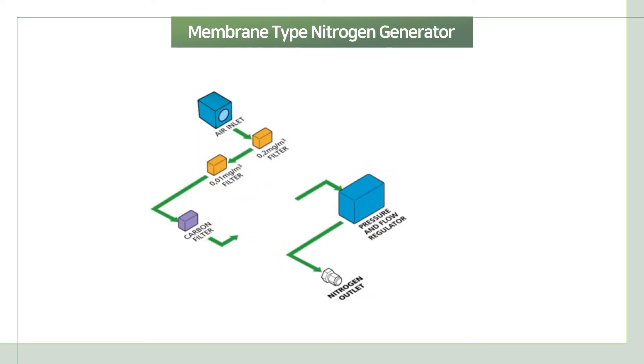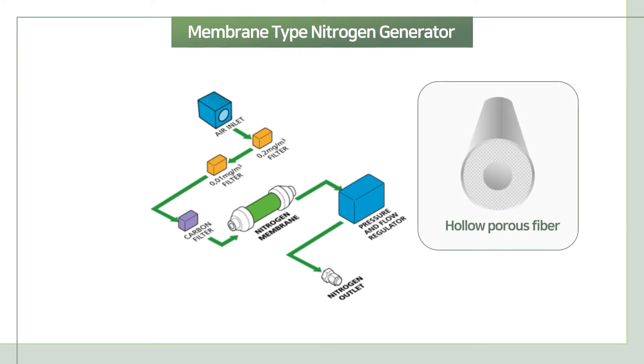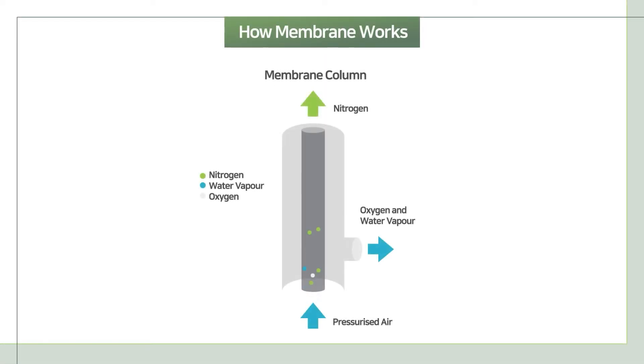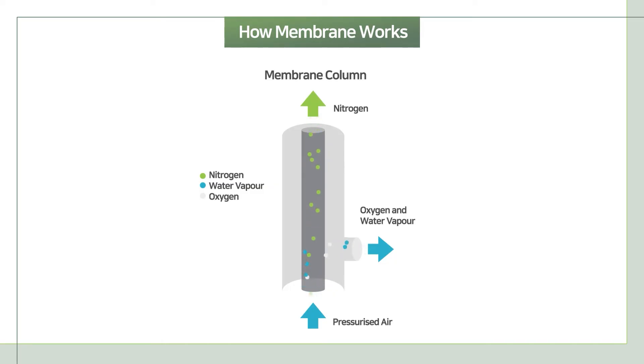The other type of nitrogen generation uses a membrane. Membrane type uses a membrane filled with a bundle of hollow fibers to separate nitrogen from air. The wall of the fibers selectively separates gas molecules in compressed air based on their diffusion rates. Oxygen and carbon dioxide are fast enough to permeate through the membrane wall, while relatively slow nitrogen is retained and passes along through the fiber.